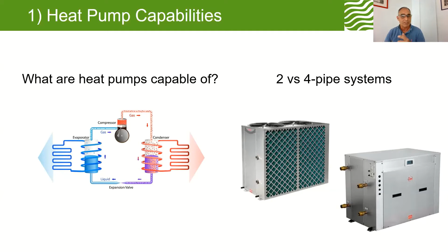On the right-hand side, we have a 4-pipe system. We have a cool loop where cool water goes in and cold water comes out on the second pipe, and then a second loop which gives us warm water going in and hot or warm water coming out. This is important to consider, because when we have a hot, a cold, and a warm side of the heat pump, we can use it for cooling, heating, or for heating and cooling simultaneously. This is a very important point for a couple of other slides we'll come to in a moment.